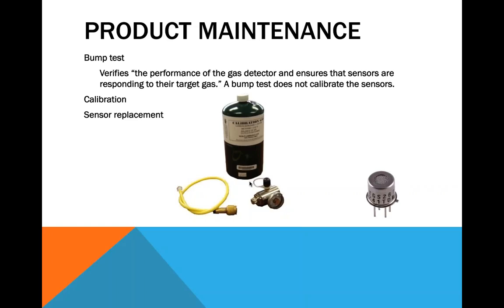Sensors also occasionally need to be replaced. They are usually plug and play. They can be inserted in the device, enter a code, or reboot the device, and it will go back to functioning normally. And you can get from 2 to 5 years, depending upon the type of sensor. Oxygen, usually 2 to 4 year range. The toxic gases like CO and H2S in the 3 to 6 year range, and the combustible sensors in the 2 to 5 year range.